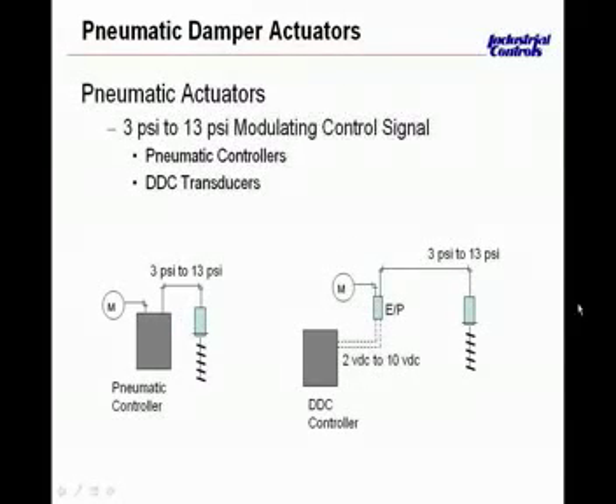And this is something that we see quite often where a direct digital control system comes in on top of an existing pneumatic control system, and in particular in the main air handling units, to be able to take direct digital control, electronic control, and still keep in the existing pneumatic actuators, either dampers in this case or valve actuators, because the existing cost, the capital investment, is already there in place for these actuators, and quite often the size of these pneumatic actuators can be pretty large, and therefore this is a better application and a better solution to continue to use those pneumatic actuators. Right, and you've probably seen this before with the electric actuator offering. To get the same amount of thrust or torque, quite often they get either very difficult to find or very expensive, whereas pneumatics can very easily and inexpensively give you a good deal of thrust or torque. So this really makes the DDC retrofit a lot more realizable.